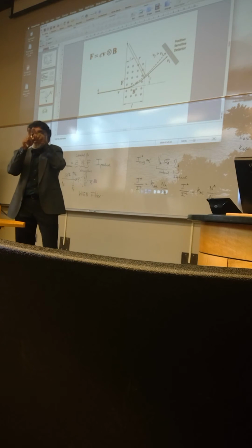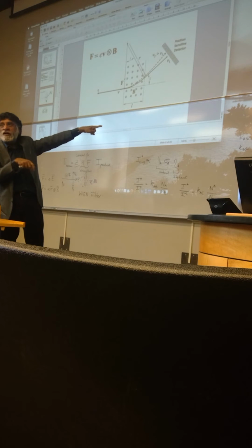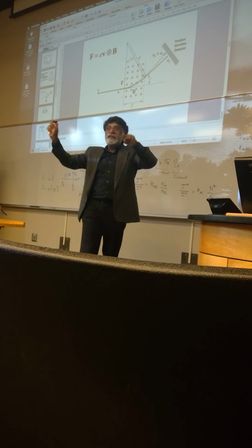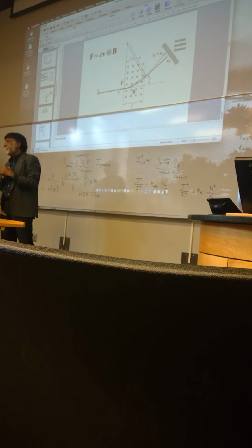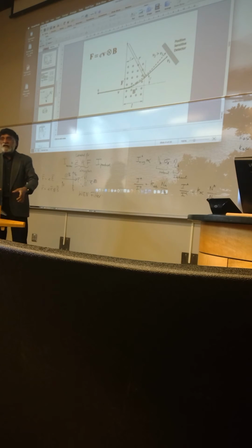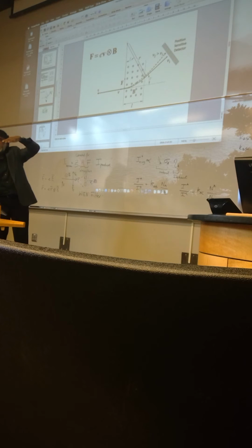Now you can either have an open slit that you can detect one velocity at a time, or you can have a position-sensitive detector that detects the intensity at different positions, and then you can have the whole spectrum displayed at one time. So if you go and see certain electron microscopes that have at the bottom an energy loss spectrometer, they're almost always designed using a magnetic sector and a position-sensitive detector.